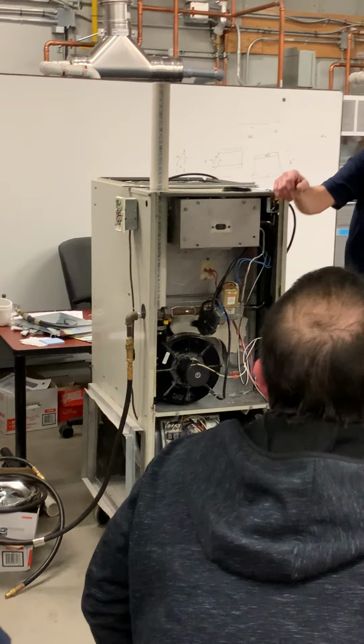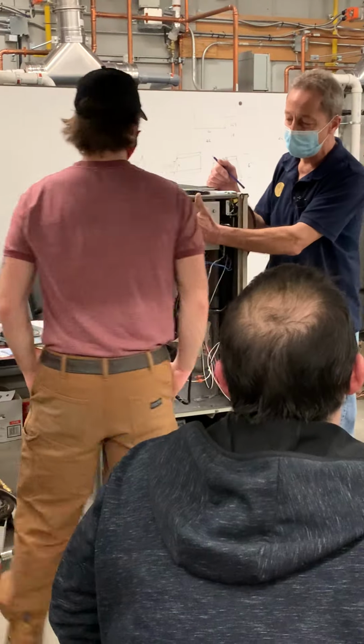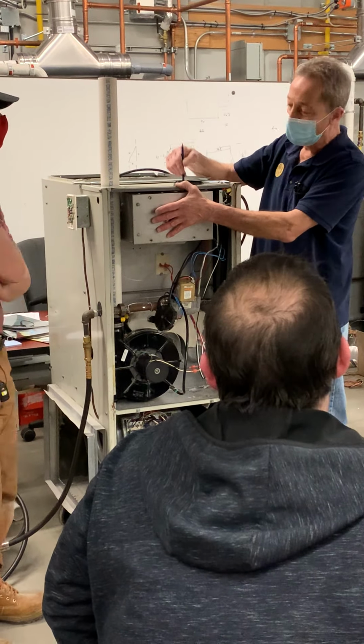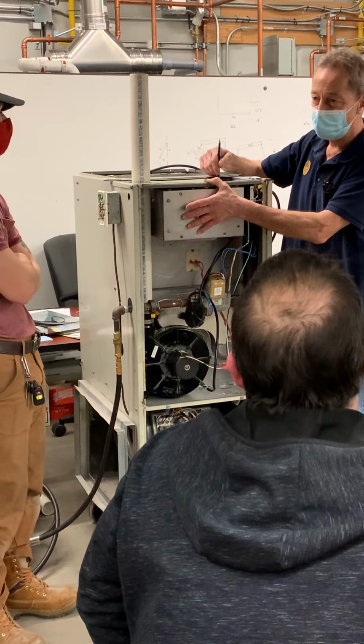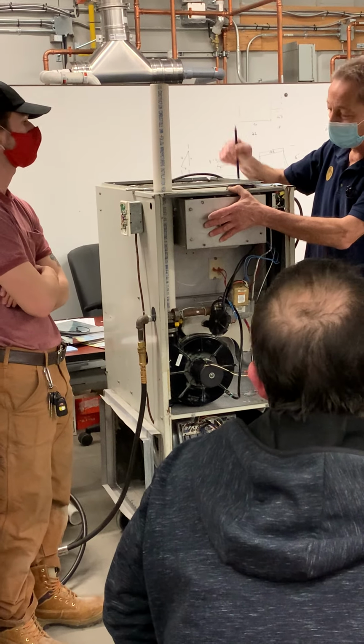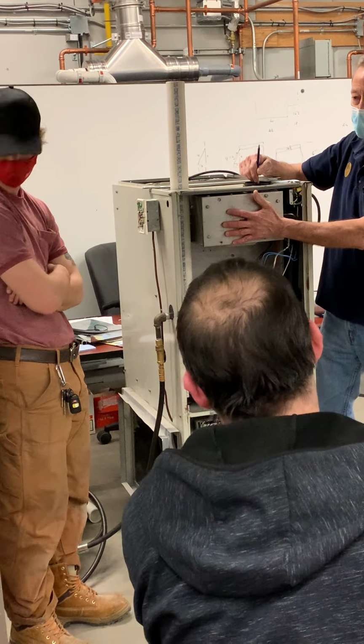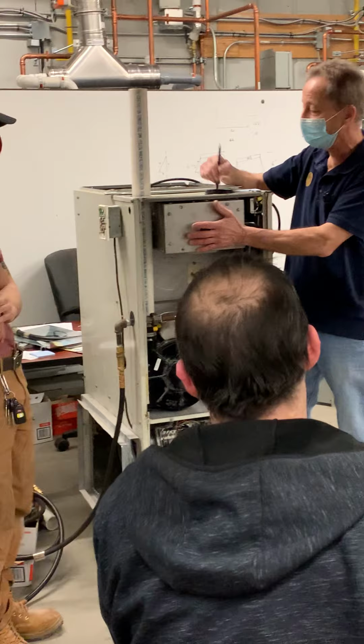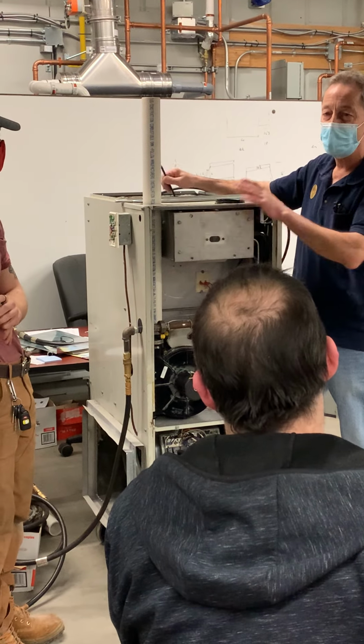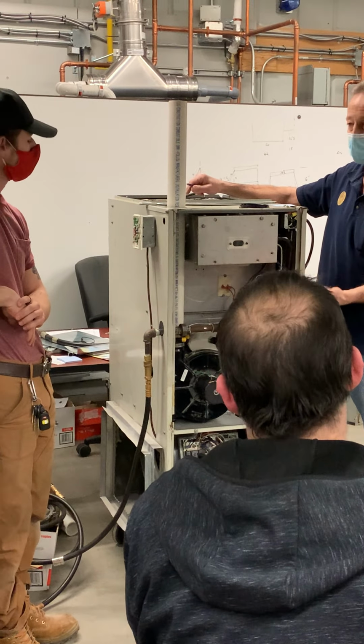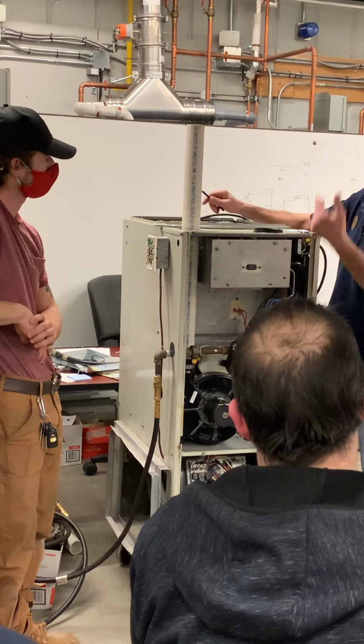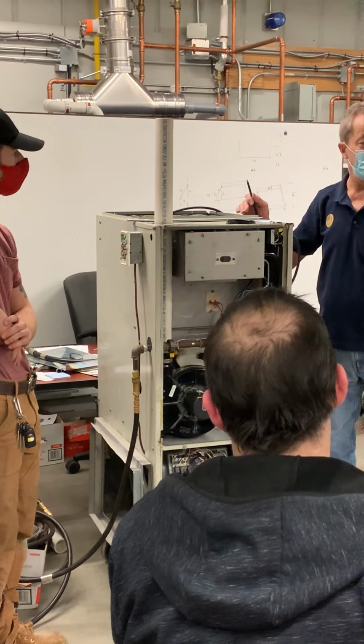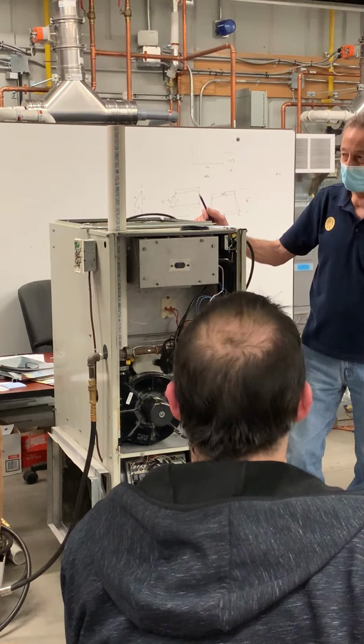Now, a sealed burner box, what does that mean? It means this area is sealed. I've got to bring a pipe over here, and that pipe's going to bring my combustion air in. When the combustion air comes in, it gets burned, mixed with the gas, it burns in the primary heat exchanger, passes into the secondary heat exchanger and condenses, then comes out the pipe here at about 120 degree flue gas temperature, give or take.